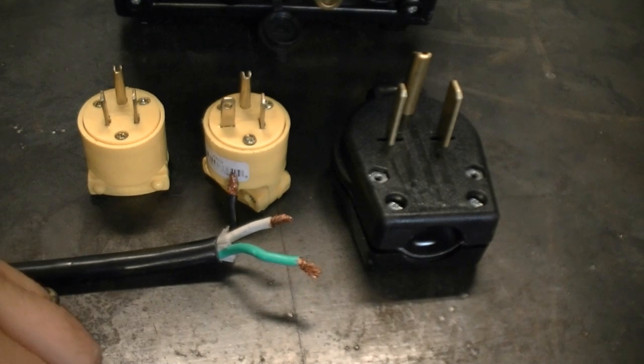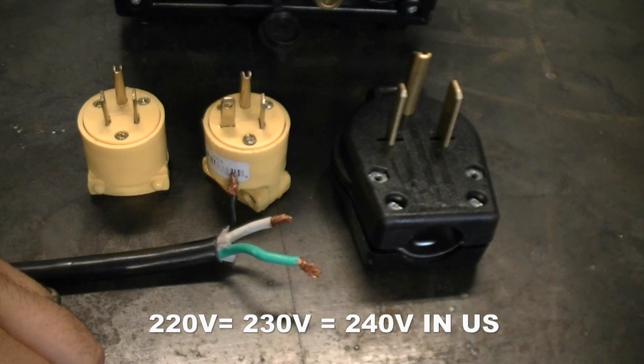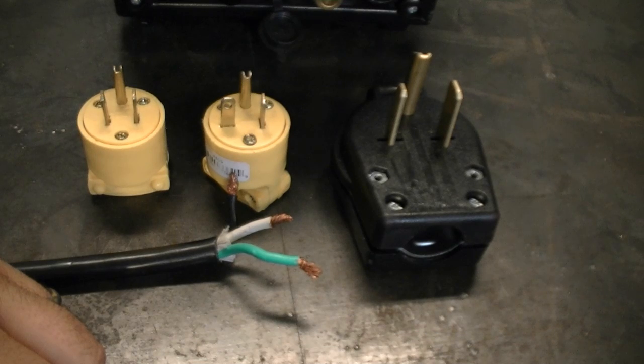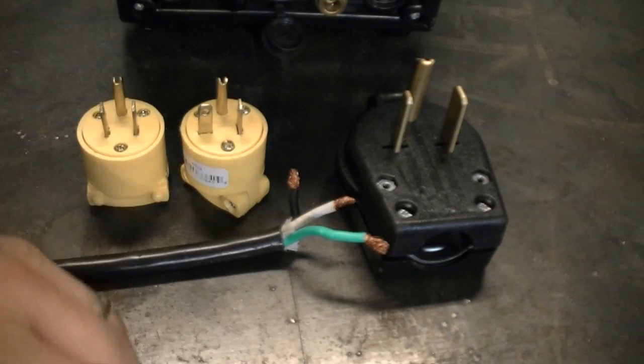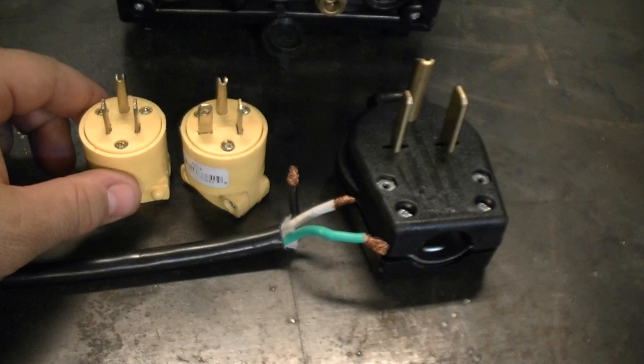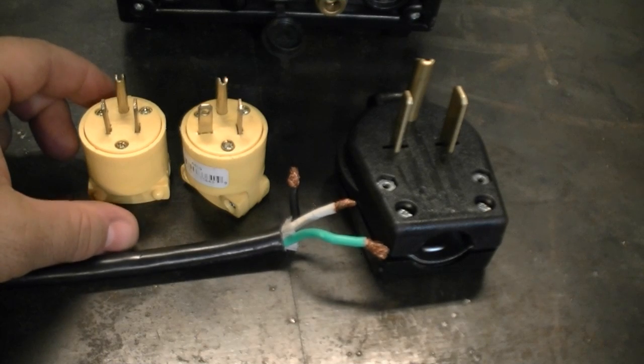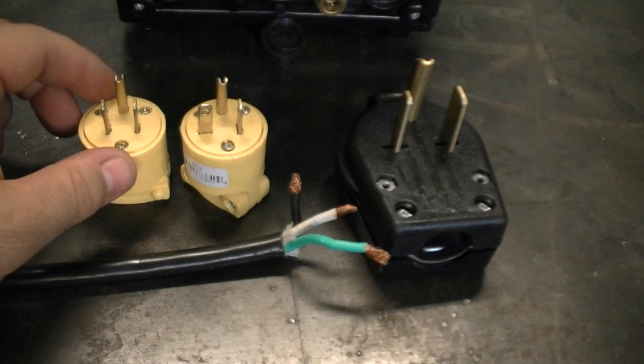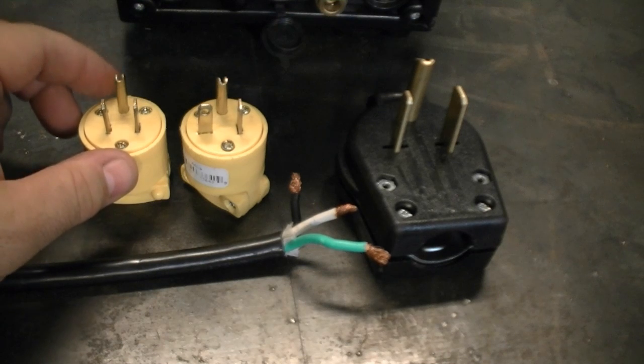For 240, you're going to see similar voltages. You're going to see 220, 230, 240, and in some cases you may see as low as 208 listed. Because of the voltage differences in the United States, you may actually find that your welder pulls more power in some localities than others.